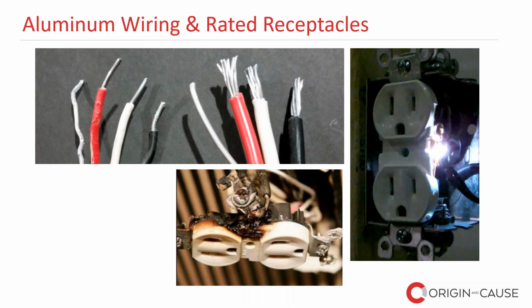There is a caution that has to be used when you're terminating them, and some scientific analysis would prove that the expansion rate for aluminum is greater than copper. So if you're not using it with the right terminations and the right connections, you can end up with loose connections and high resistance faults, and this can lead to a fire.